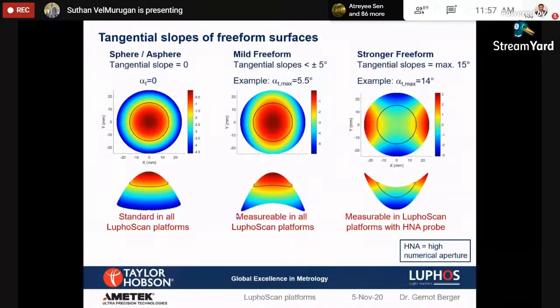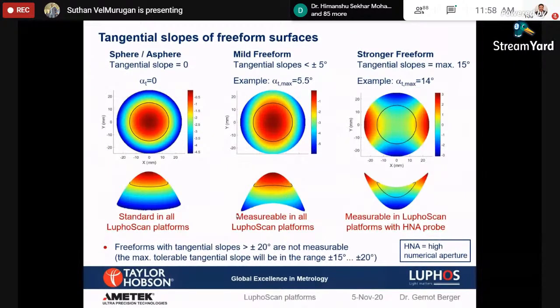If it is more than 5 degrees up to 15 degrees, we may need a special HNA probe. We call it HNA, meaning high numerical aperture probe, which will go very close to the part so that the slope will be minimized. It can collect the reflection from the sample or from the optics, and then it can analyze it. So this is a special or custom-made solution available for free-form measurement. Yeah, hopefully I covered all the topics.